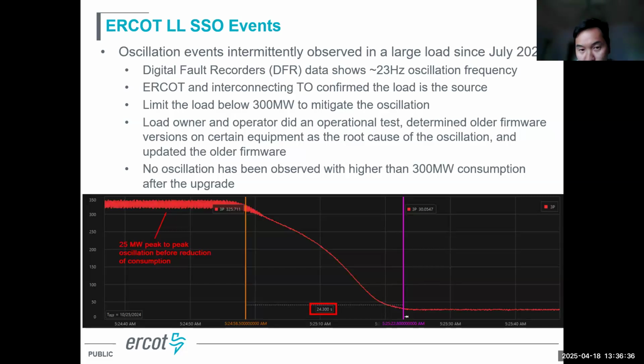Since July 2024, for one large load, we observe oscillation all the time, especially when the dispatch or consumption is very high. Initially, we identified this one in the EMS. The frequency looked like 8 hertz or something. But later we requested the DFR data, and it shows the oscillation frequency is about 23 hertz. And both ERCOT and the TOs, the transmission companies, confirmed the load is the source. What we found is that if we limit the load below 300 megawatt, then the oscillation goes away.